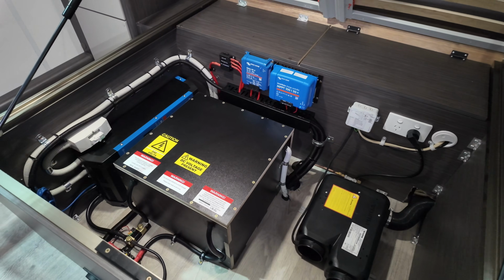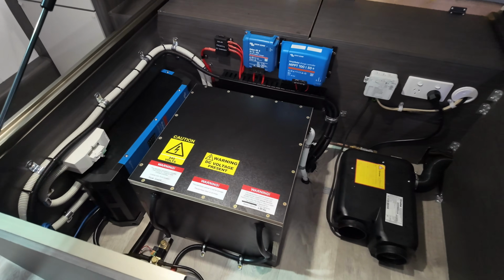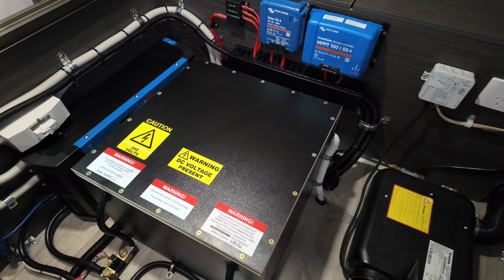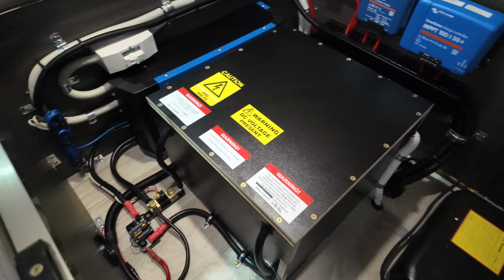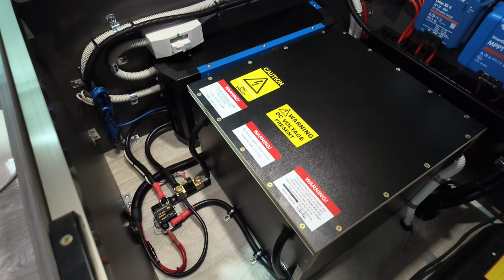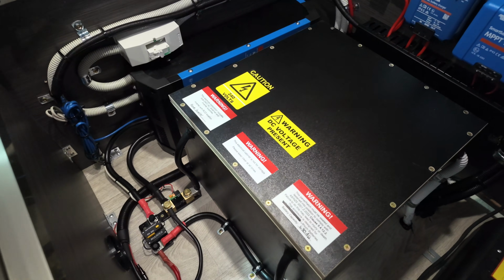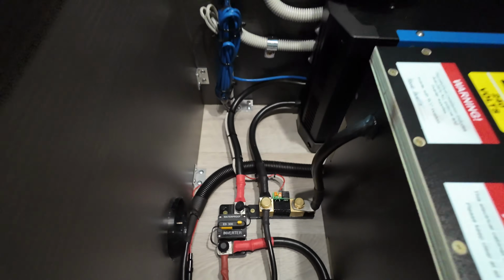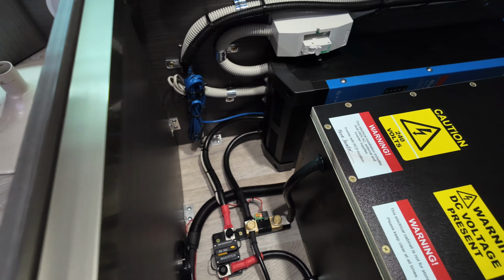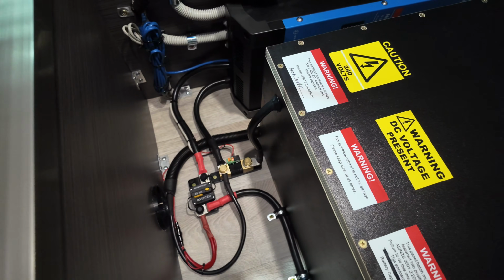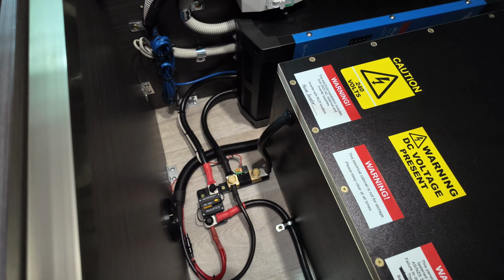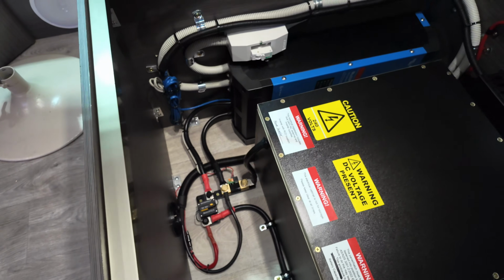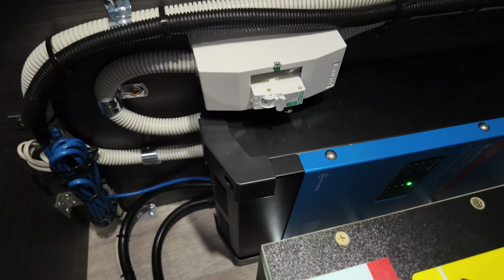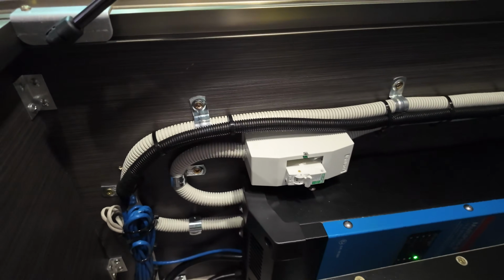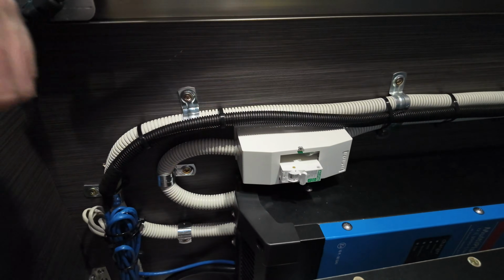This Jayco All-Terrain is now finished. I've got the battery box with all the AS3001 stickers, a 300 amp manual reset circuit breaker for the inverter. You've got your shunt there, that's our battery monitor, I'll show you the screen for that in a second, monitoring the whole system. Got an inverter with our RCBO, I just need to put a pole filler in there.